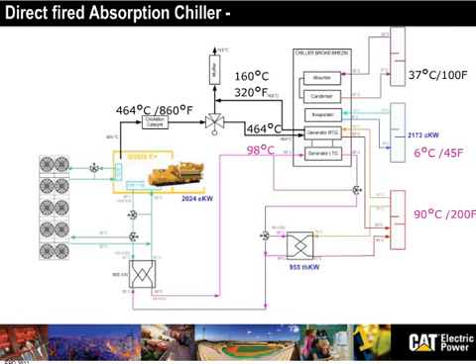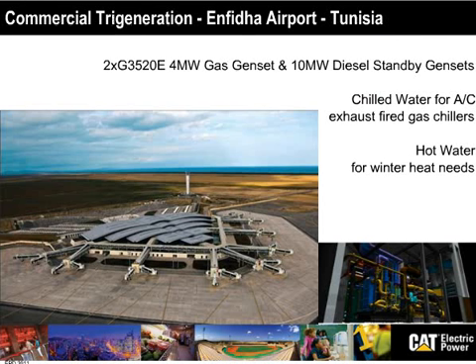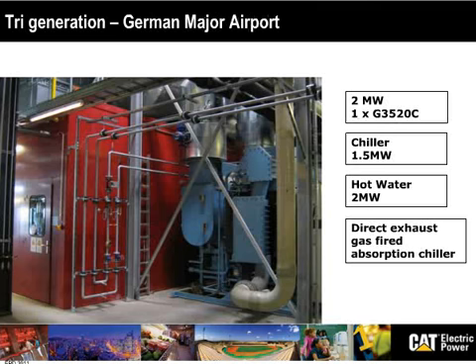So in the chart here, you see a direct-fired absorption chiller, and you have production of cold water at 45 F and 6 degrees C. And also for the winter time, we have this 90 degrees C for heating. This was implemented in this airport in Tunisia, where we use the chilled water for the summertime and hot water for the winter time. Chillers are very popular in airports. Here is another one in Germany, in one of the major airports, 2 megawatt. 1.5 megawatt chiller, chilled water for the summer, hot water for the winter. Again, direct-fired absorption chillers you can see on the picture here.